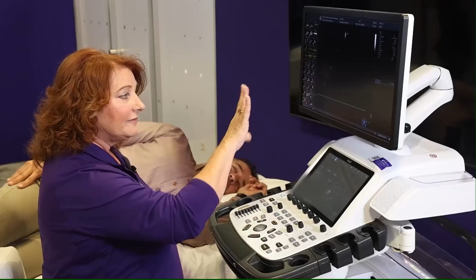Now, when we first get our pictures, we start in the apical position. When you get your image, you want to take a moment and fine-tune your picture. Even though you've done starting settings, every patient is different. For instance, we may need to adjust the MI up or down depending on the patient, their size, and what we're seeing. If we don't see the basilar area of the image, we may need to increase our mechanical index to make that happen. Same thing with your compression.